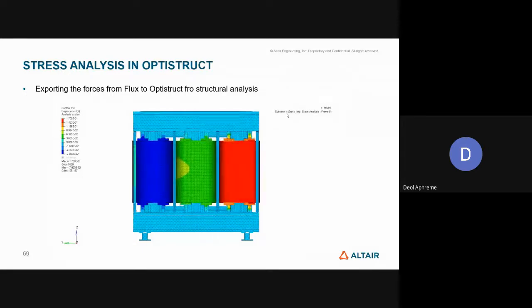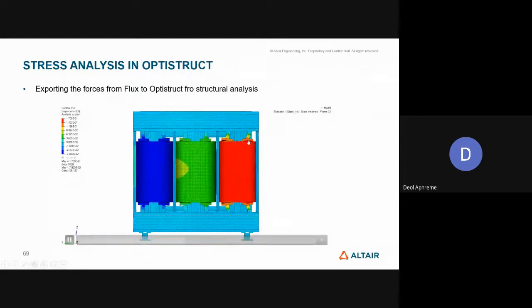Where would breakage first occur? Even if you are going to visualize a transformer that has been in use for 20 years, if it's a very big complex transformer, you want to know where to look. You will see the maximum stress points here. As you can see in this GIF, the upper point and the lower point are in red, which basically means the maximum amount of force is experienced there. So it's throwing this entire thing for a toss.